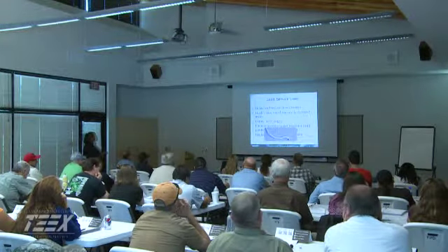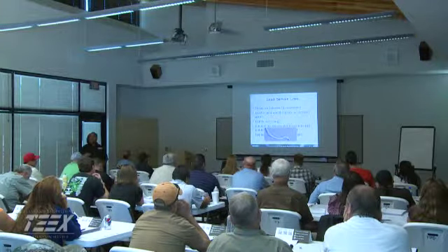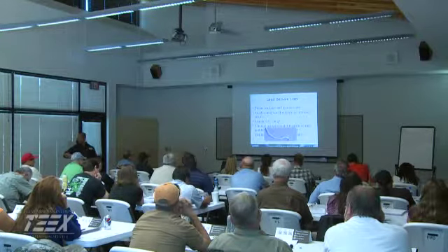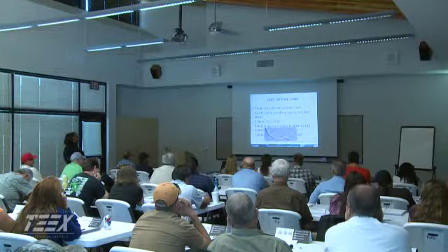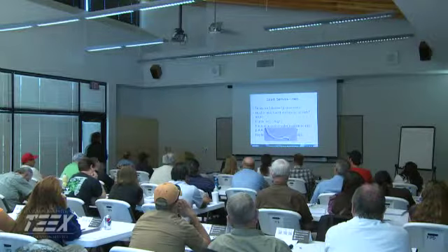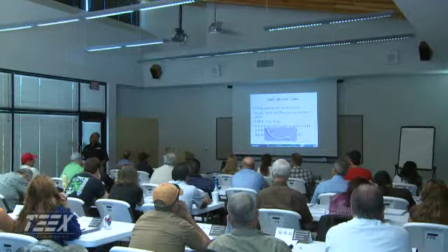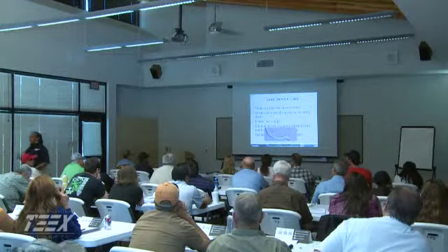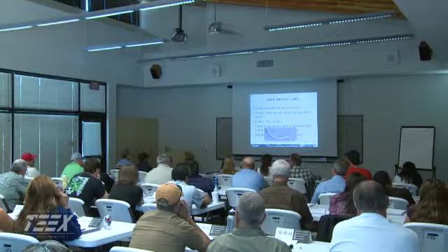Lead service lines are rare today because of that 91 rule, lead and copper. Replacement was put in place where you had to show you were removing at least 7% of your lead service lines. We know lead to be very toxic, and it dissolves in corrosive water. In other words, as we're sleeping at night, lead and copper can be leaching out into our water. So when you get up the first thing in the morning and take that first sip, it could be laden with lead and copper that exceed the MCLs.